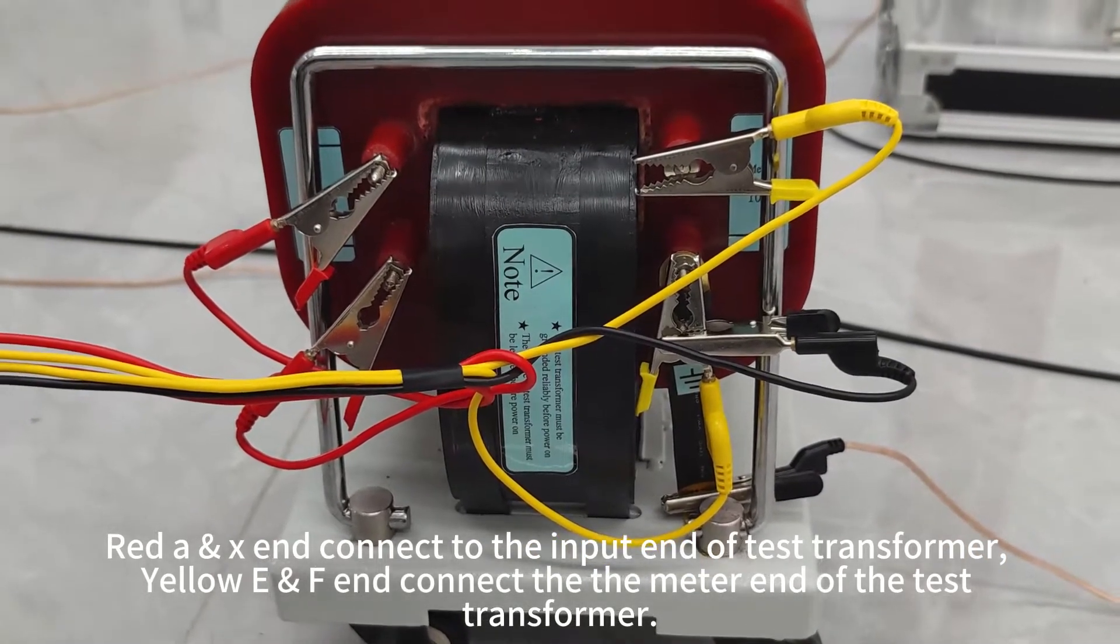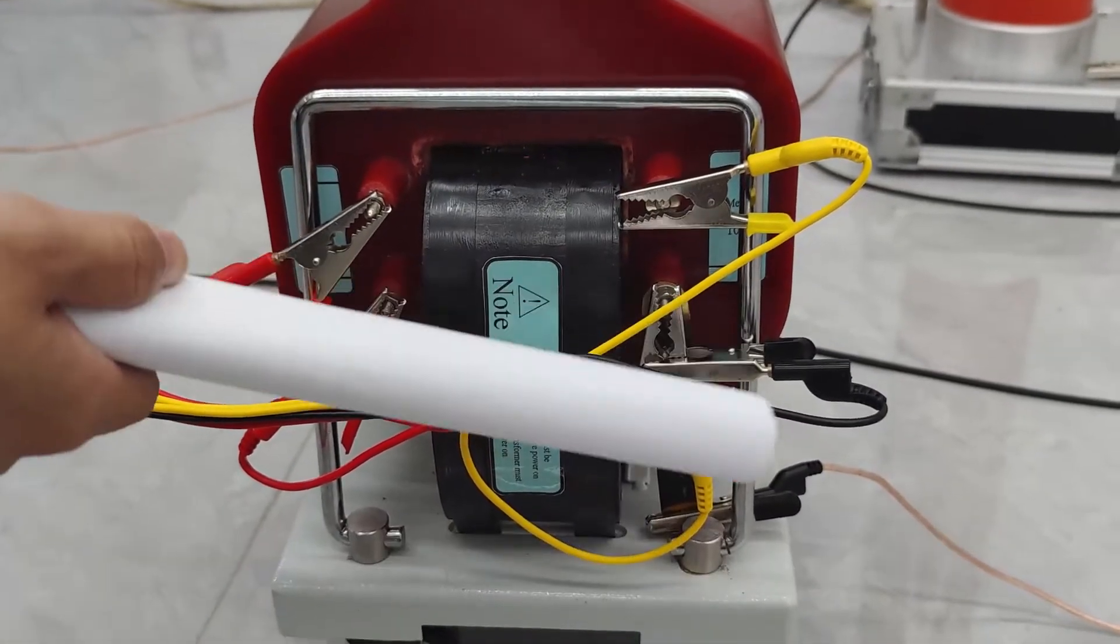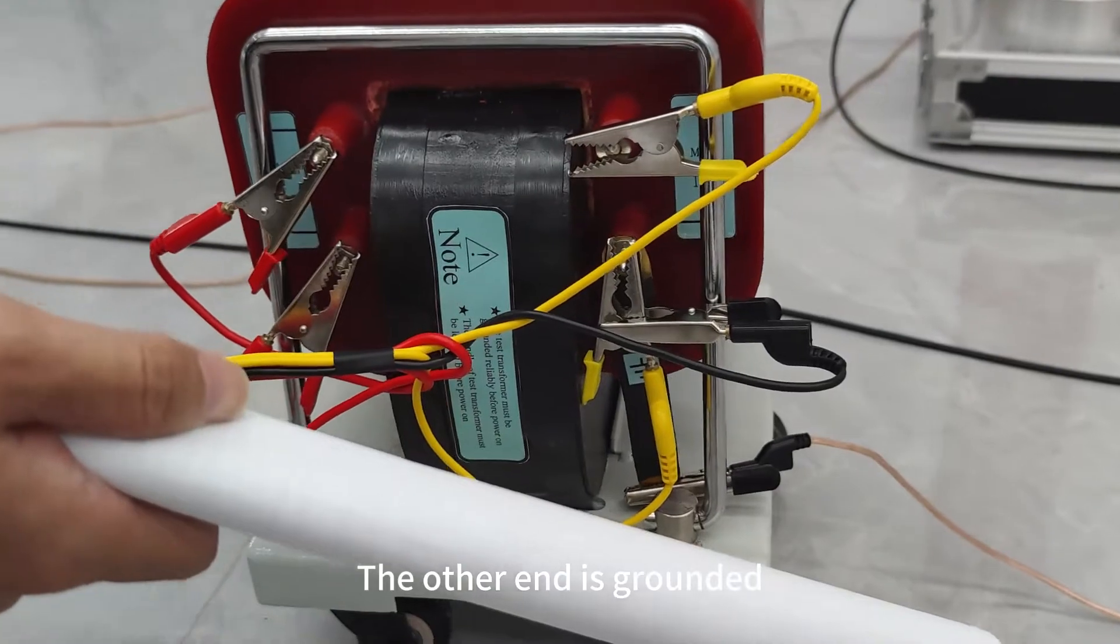Yellow E and F end connect to the meter end of the test transformer. The other end is grounded.